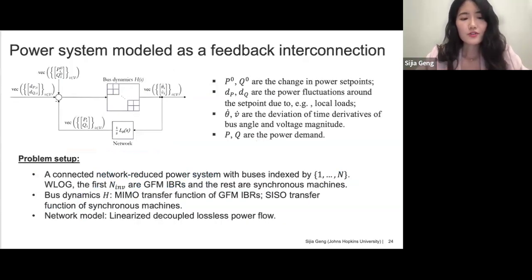In this project, we consider first a mix of droop-controlled grid-forming inverters and synchronous machines. Consider a connected network-reduced power system with buses indexed by 1 to n, and without loss of generality, assume the first N_inv are grid-forming IBRs and the rest are synchronous machines. The power system is modeled as this feedback interconnection as shown in the block diagram here. The forward path consists of the bus dynamic matrix H. And for the bus dynamics, the grid-forming inverters are modeled as multi-input, multi-output transfer functions, while the conventional synchronous machine is modeled as a single-input, single-output transfer function for its second-order angle dynamics.